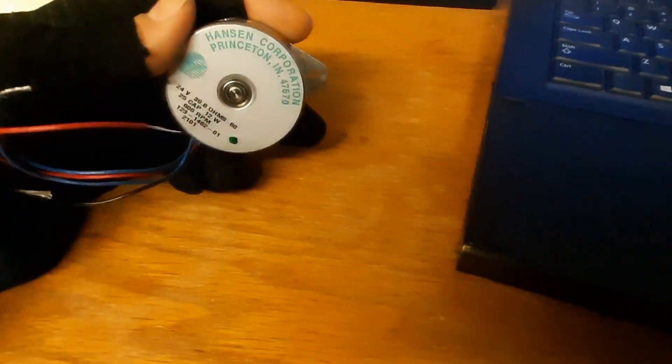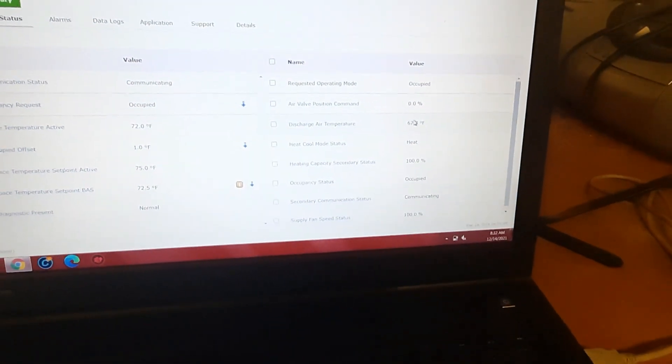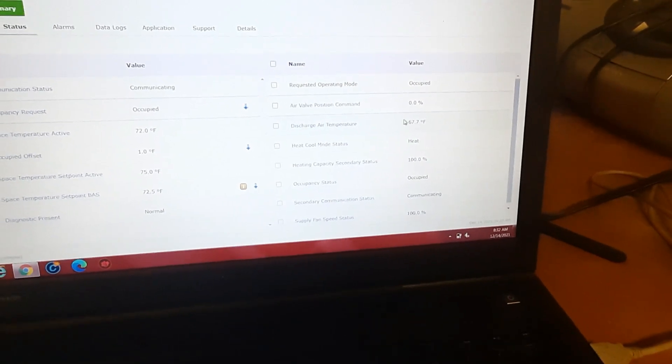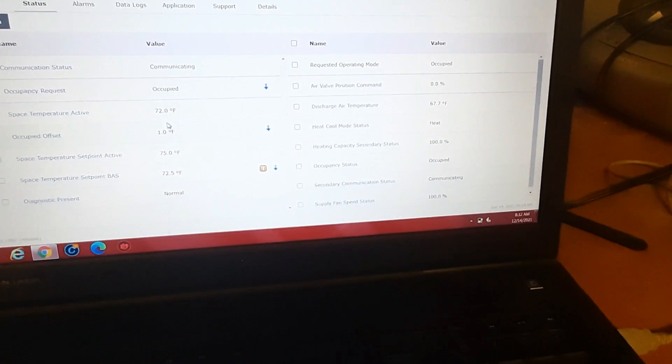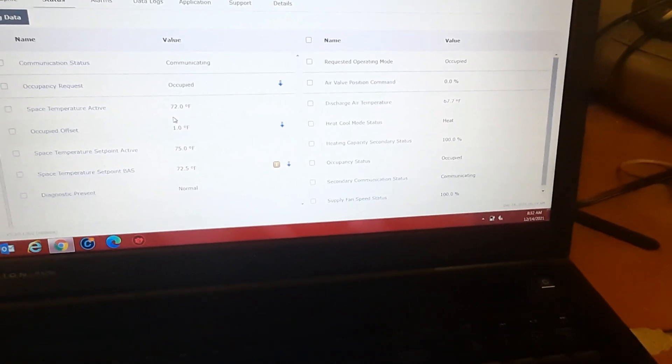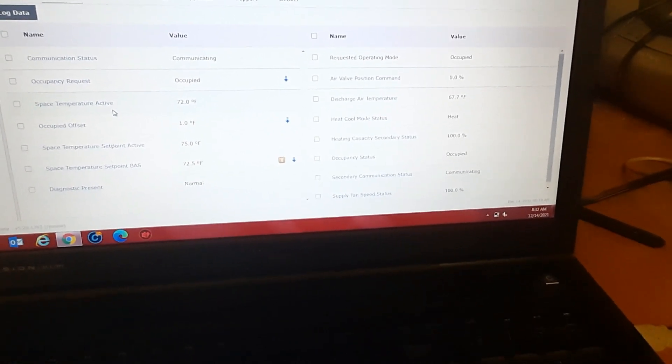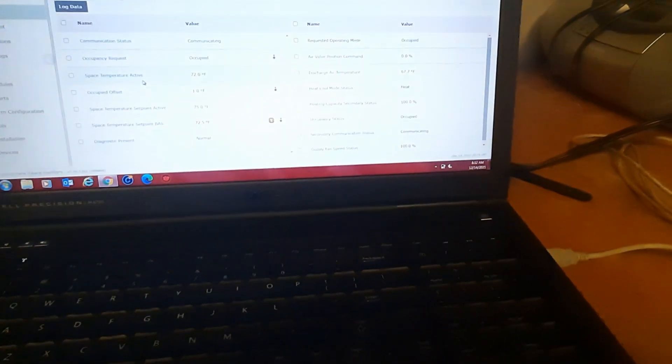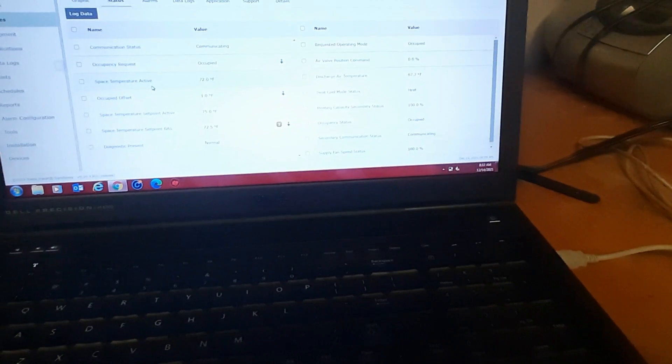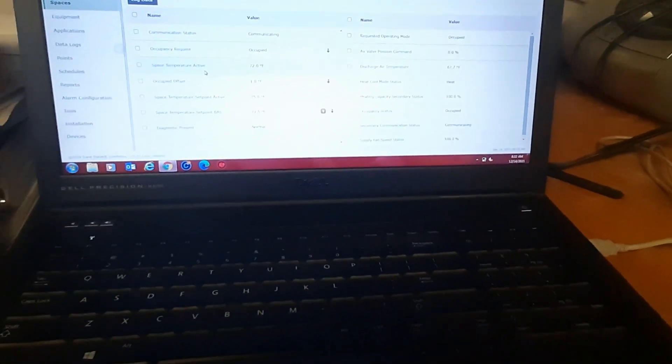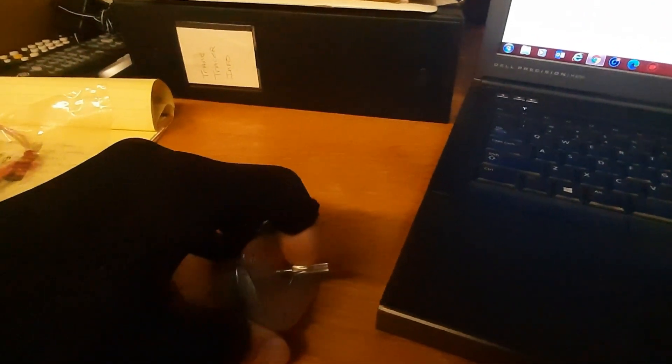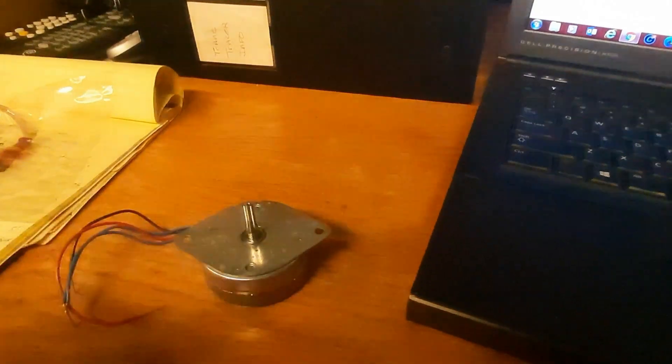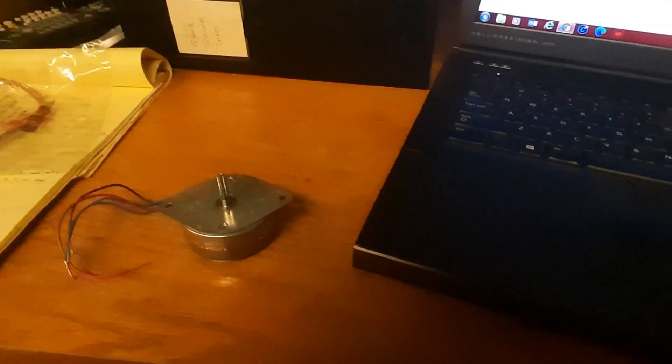Let's get up there and take a look at the box. We're going to get this actuator in and then see if we can't get this supply temperature. But 80 to 90 degrees should be sufficient to heat the space. It was 66 degrees or something in there yesterday before I adjusted a little bit. But the actuator is clearly, bearings are failing on it. A lot of times what they'll say is it sounds like a hamster in a squirrel cage is how everyone describes it, because you can hear those things rattling as it's trying to turn and skipping and stripping the plastic, the wheel gear that actually fits on here is plastic.